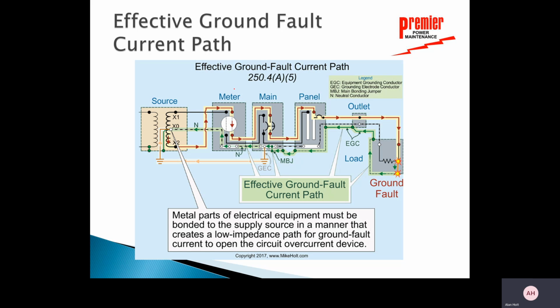So we're back to our separately derived system here. There's my source, okay? Got my meter, got my main, got my panel. And if you'll notice that in this situation, my main supply panel is tied to earth right here, okay? Now I also know that the transformer is tied to earth back on the pole. And I see a light orange line here. They're both going to ground. So I can have some ground current flowing there. But what I'm worried about is from here on back.